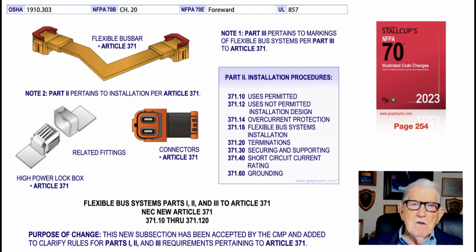And of course, Part 2, we're dealing here with installation procedures. You're dealing in the boxed in information with 371.10 through 371.60. Now, that's what this illustration is illustrating, that we're dealing with a flexible bus type system. And Part 2, the sections are listed there that deal with particular subject matters, such as 371.20's terminations, 371.60's grounding. In other words, you can just review this and you know the part that you need. You may say, well, I want to know where it's permitted to be used. Then that would be 371.10, use is permitted. 371.12 is use is not permitted. So everything's kind of given there for your use, and it'd be important to review either one of these section numbers if you're dealing with installation procedures, and that's what this illustration is illustrating.